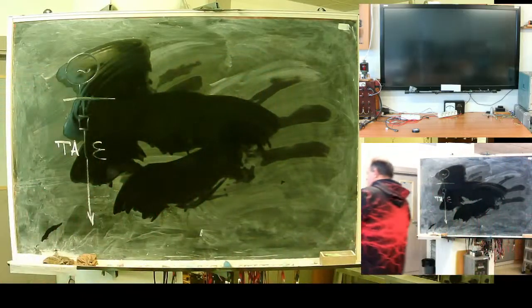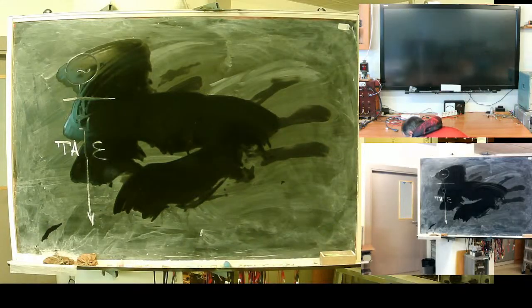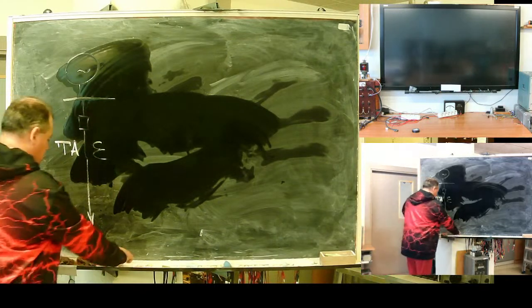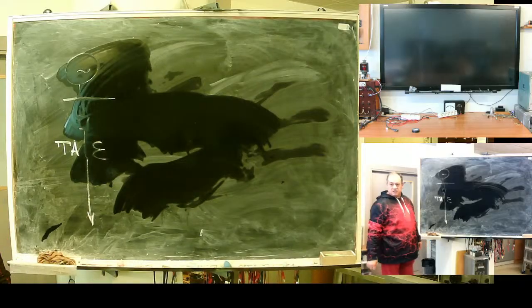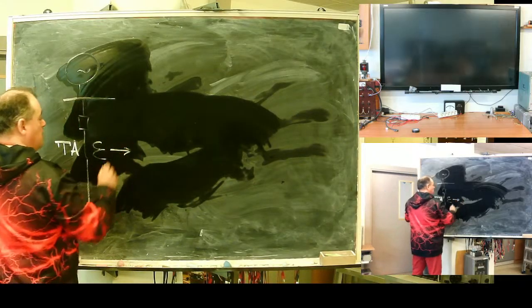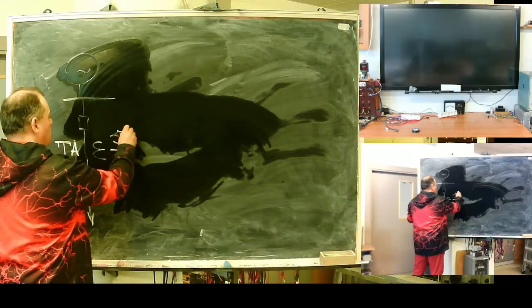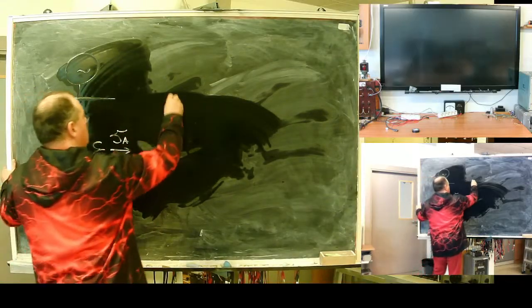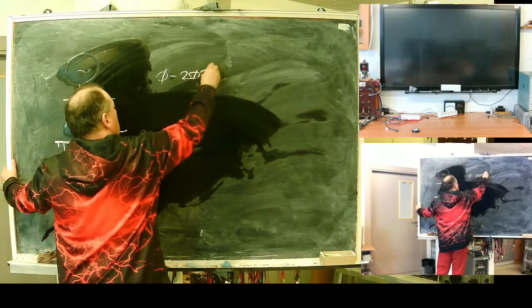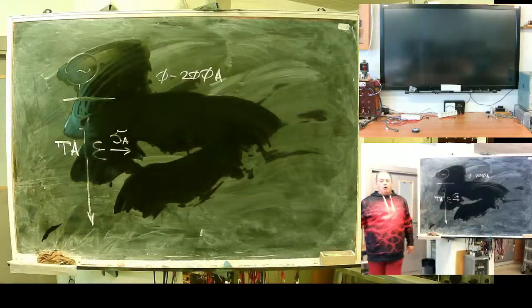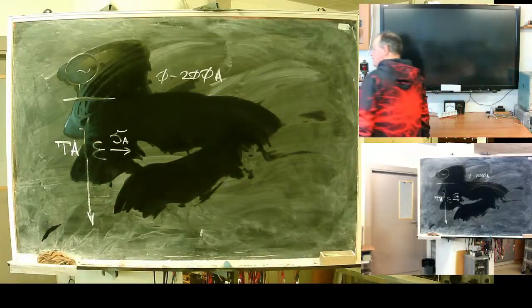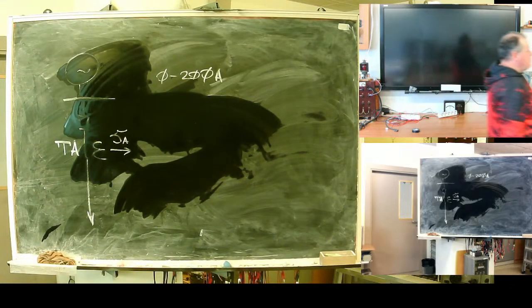Here is a terminal for 10 kilovolt current. T means transformer, A amperes: current transformer. From the current transformer we have a signal with level rated 5 amps. In reality it has from 0 to 200 amps. In the older style, analog style, we will get 5 amps. Here it is grounded.